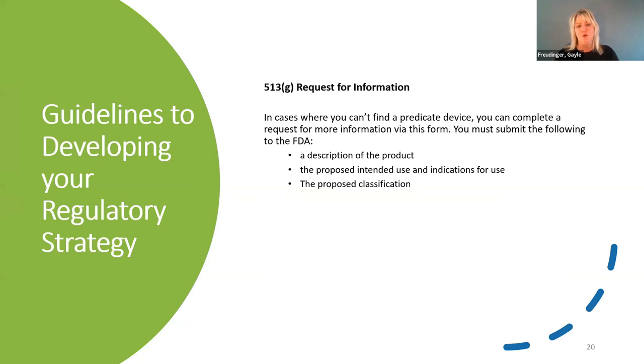Now what happens if you can't find a predicate device? This would probably be a good time to initiate a conversation with the FDA, rather than going blindly trying to figure out what class your device falls into, and maybe you missed a predicate device that was out there somehow. You really should complete a 513G form, which is a request for information from the FDA, and you must submit a description of the product, the proposed intended use, and indications for use. Again, indication for use is always going to come back to you. You're going to have to do that up front. And then the proposed classification to the agency for review.